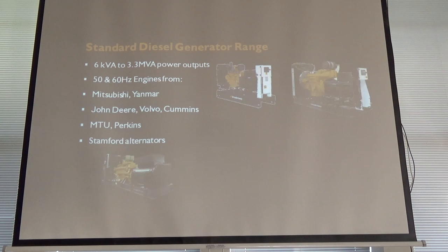So, the flexibility as well is there because we can use different engine manufacturers. And you'd be shocked at the actual differences between some of the engines for a given output, the airflow differences, and also the performances for load acceptance, load steps, etc. It's quite surprising. So again, the range, 6 kVA to 3.3 standby, power outputs. 50 and 60 Hertz units.